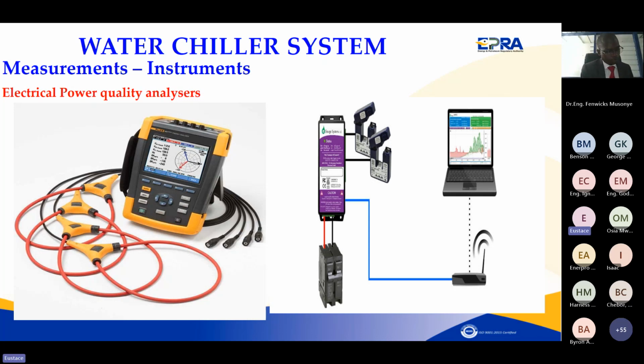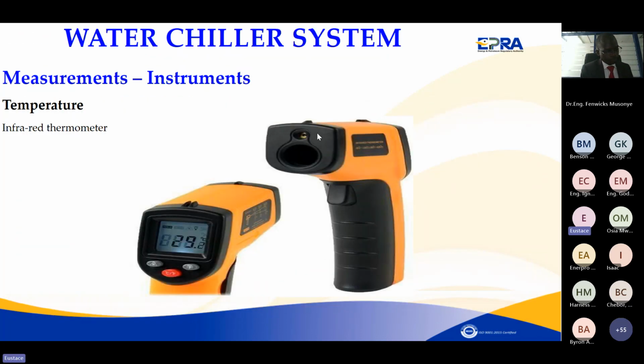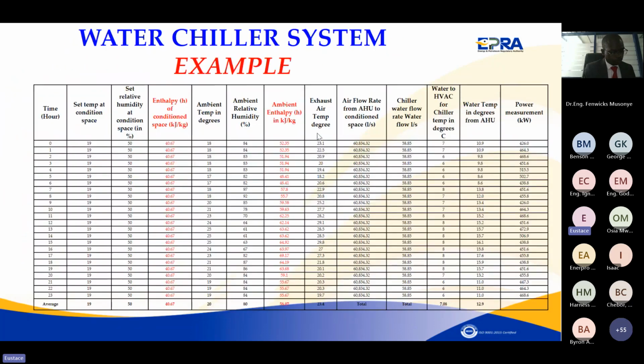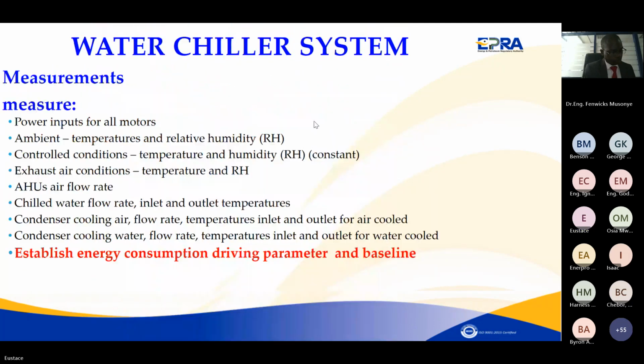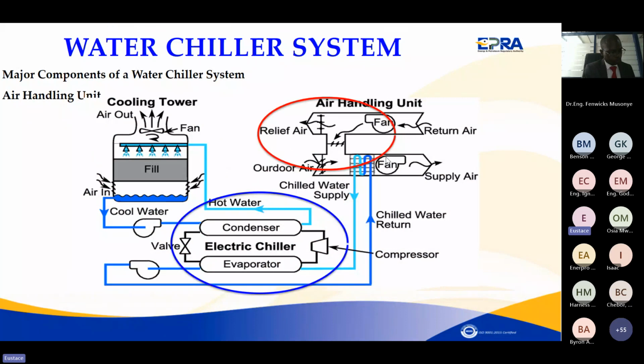Sometimes when you go to a data center, as we've said, you see there are several motors. It's good to advise, especially if you're doing a design—since some of us are engineers—to make sure all these are centralized on a good control board. Because sometimes you find the water chiller is being operated from one point, while the compressors and fans are operated separately.